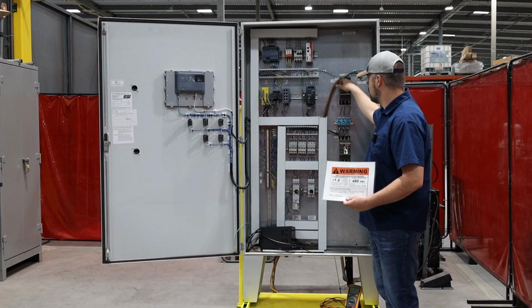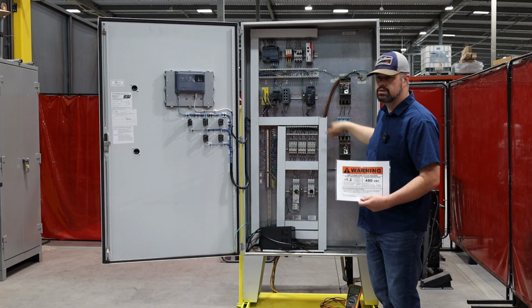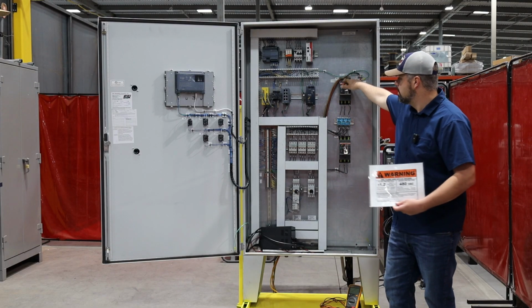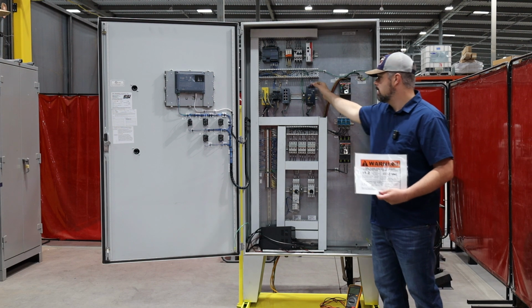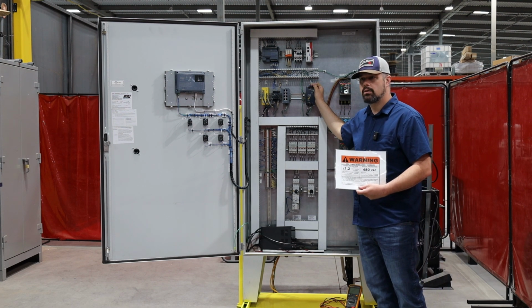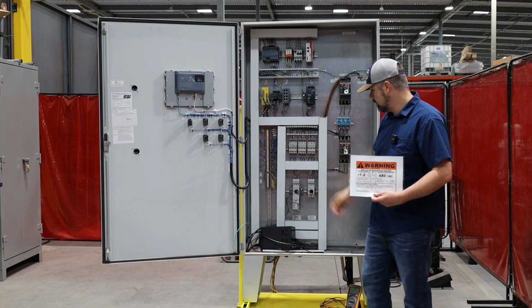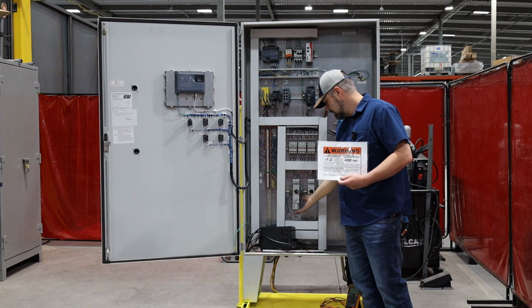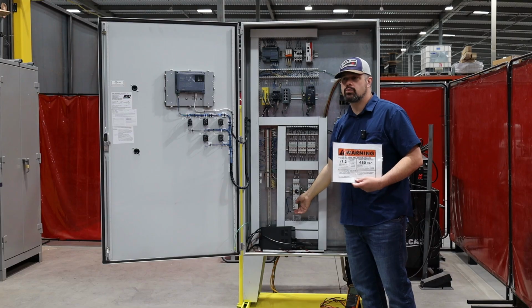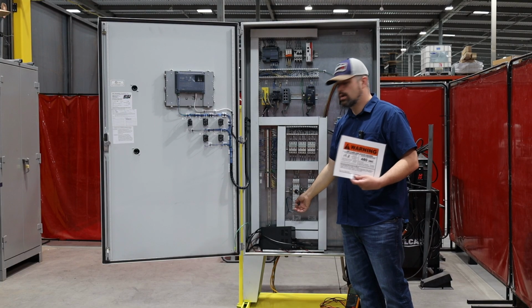So, okay, we killed power here, we verified it's dead here, and there's an absence of voltage in the panel, but we still have voltage here. Okay, so we know we cannot do any work here, right, because we're within 18 inches, but could we reseat a wire down here on this relay? We could, right?